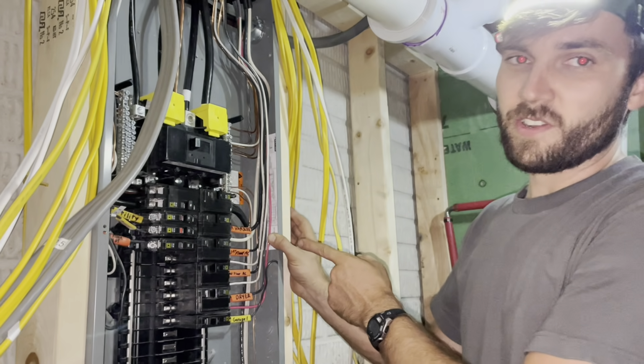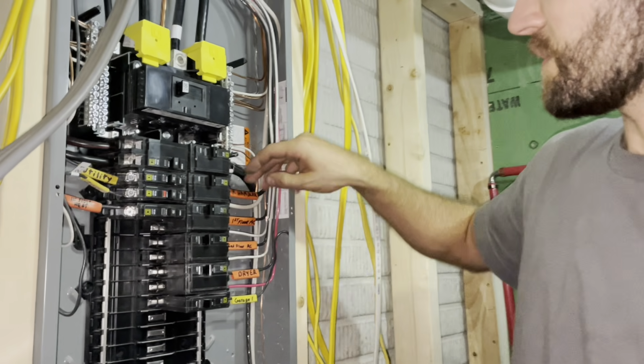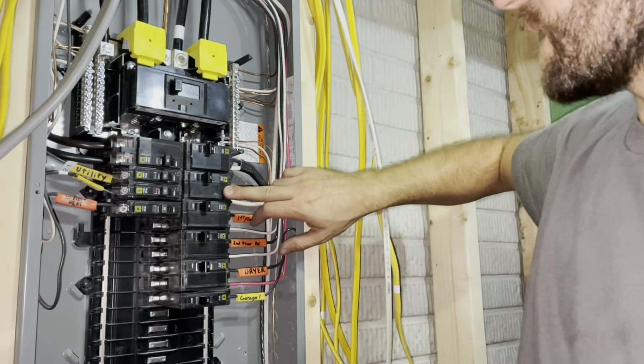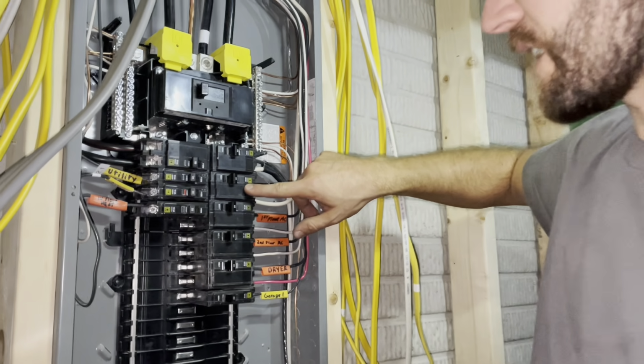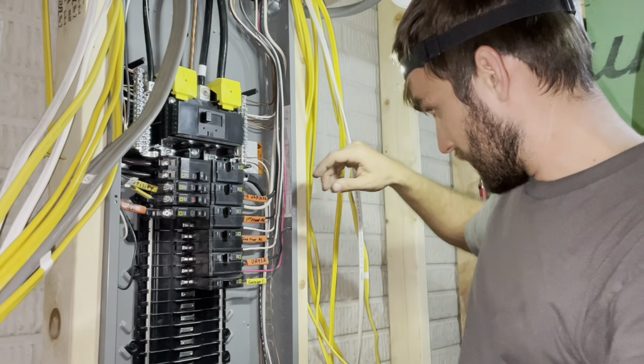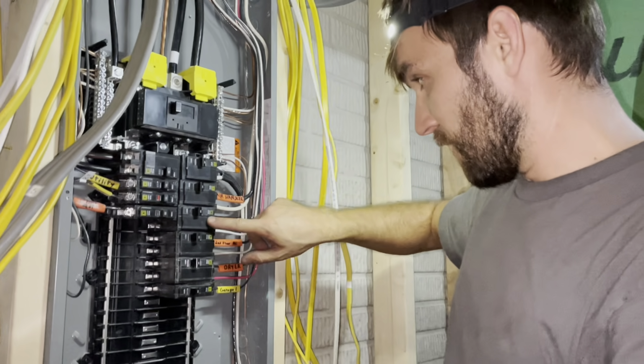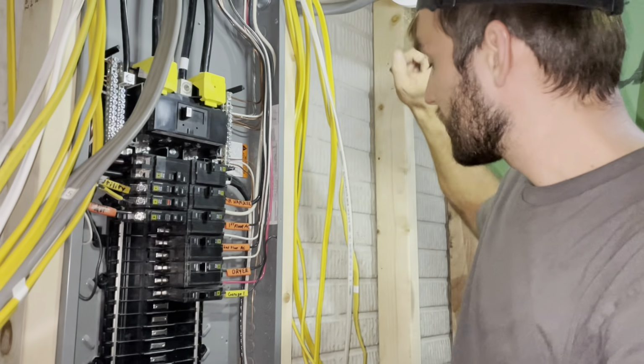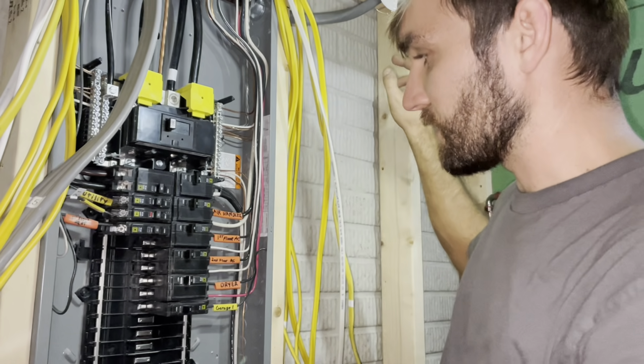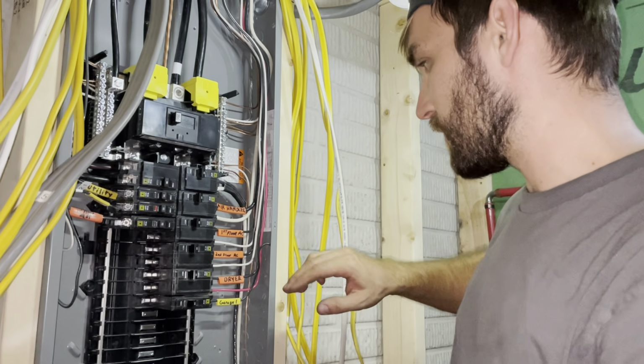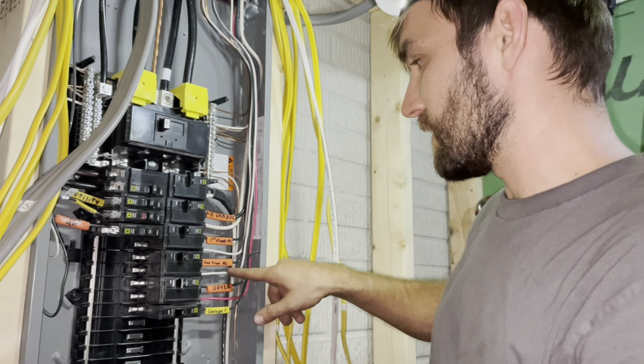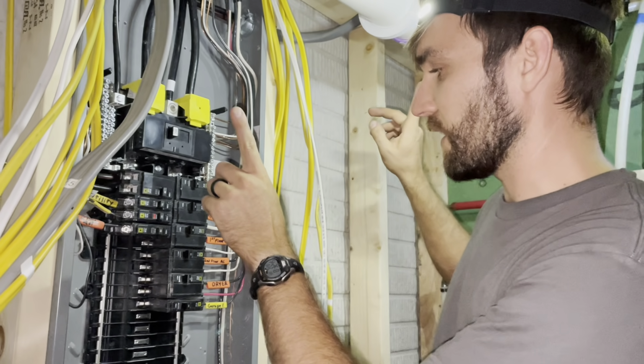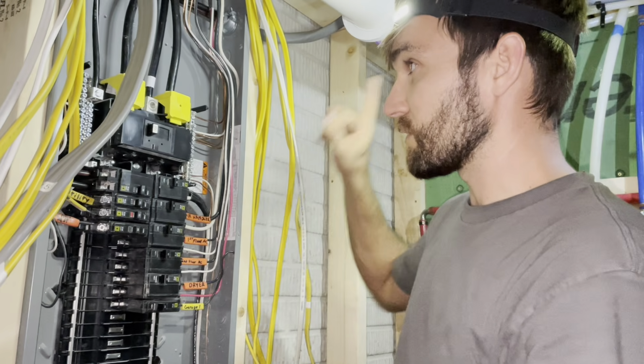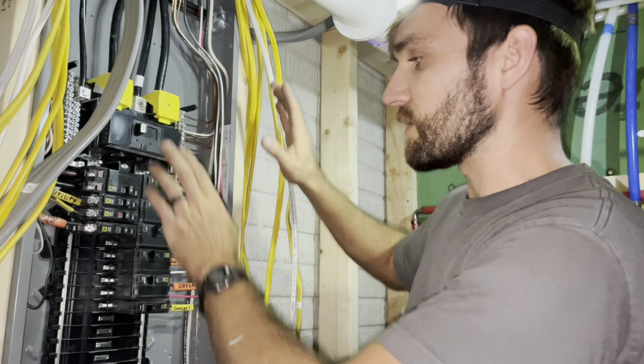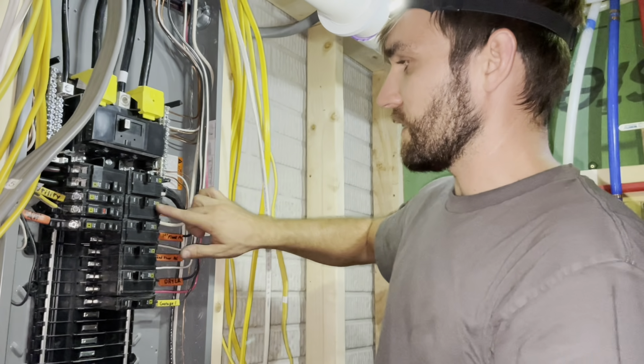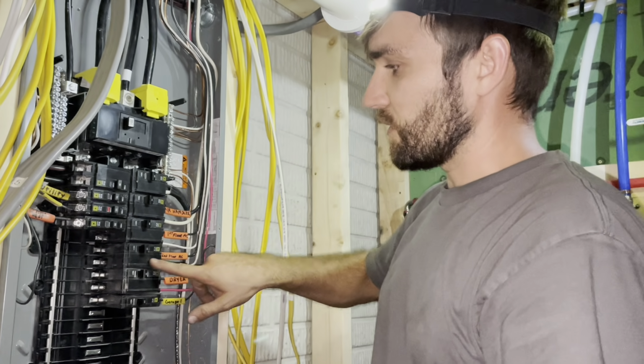All the breakers for the air conditioner equipment are hooked up now. So here's 50 amps for the air handler. That also handles the backup heat strips that are in it. And this is the outdoor unit, first floor AC. And that's 25 amps, that's what the equipment says, so a 25 amp breaker for that. And then this is the second floor unit, so the 2 air handlers upstairs. Those air handlers are powered by the outdoor unit, so they don't get their own circuit like the air handler has. And that's a 20 amp.